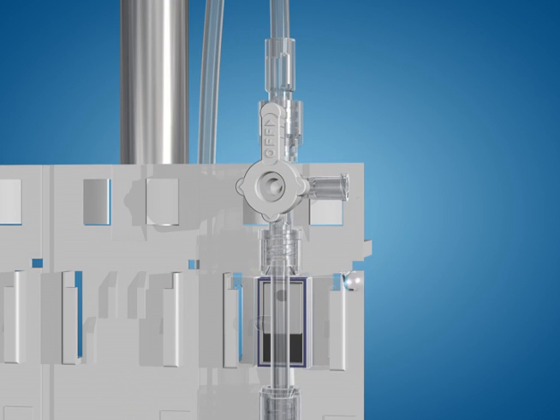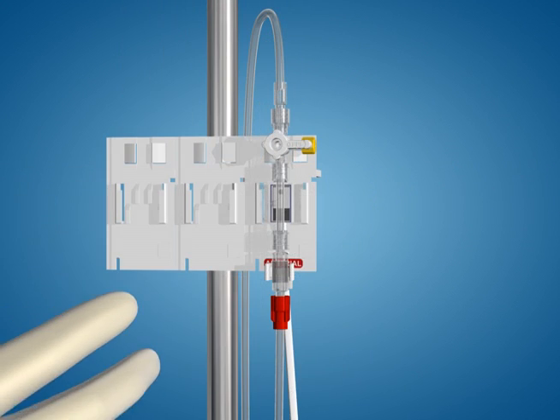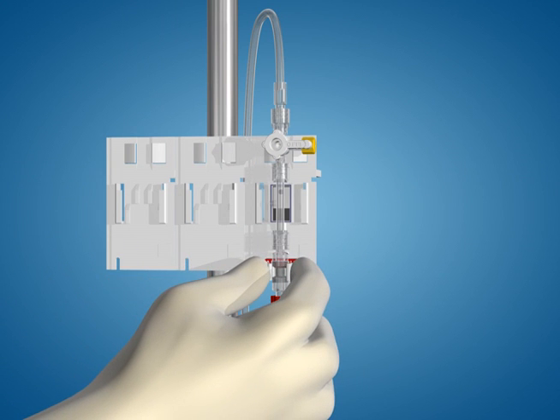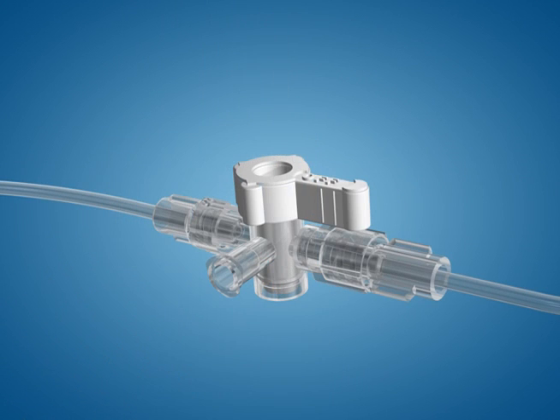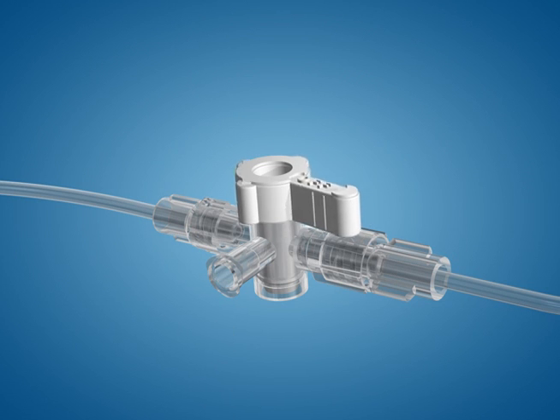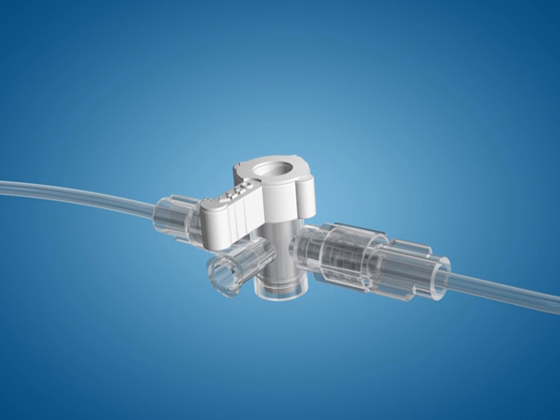Flush until fluid exits the side port of the zeroing stopcock. Turn the zeroing stopcock handle off towards the zeroing port. Cover with a yellow non-vented cap. Activate the flush device to flush the remaining patient line. If additional stopcocks are in line, ensure that fluid exits each of the stopcock's side port. Verify that all of the stopcock handles are turned off towards the side ports and that the side ports are all covered by yellow non-vented caps.